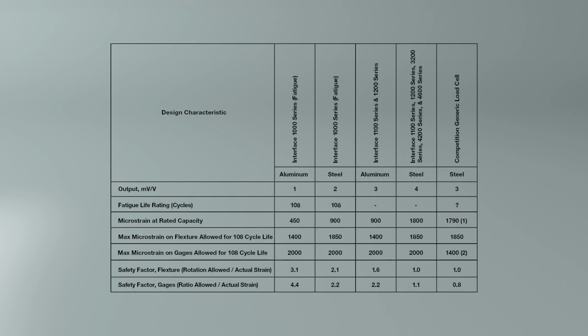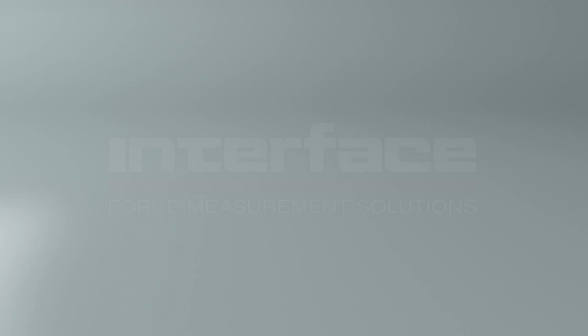Interface conducted design verification tests to substantiate the theoretical life predictions by means of actual load tests of the product. The analysis of the test data showed that there were no indications of fatigue failure nor degradation of load cell performance outside specified limits.